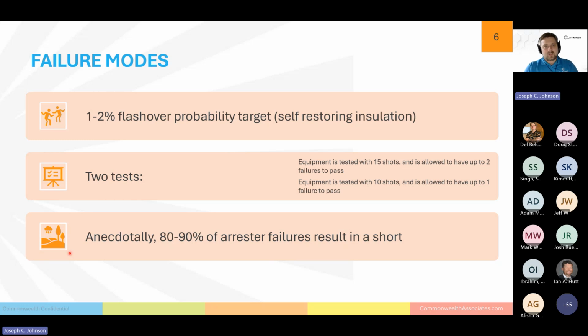So in terms of that probability, aim for about 1% to 2% flashover probability per event. And that's for self-restoring insulation or external insulation. So that's based on 2 tests with 15 and 10 shots. The 15-shot test, basically 15 different waves that we create in the lab. We don't actually go out and hold up a lightning rod and make sure something comes in. When we test our equipment that way, we generate a wave and send 15 or 10 of them, and the 15 shot is able to have up to 2 failures, and the 10 shot is able to have up to 1 failure. I have always been bad at stats. I have no idea how that equals 1% to 2%, but apparently it does.